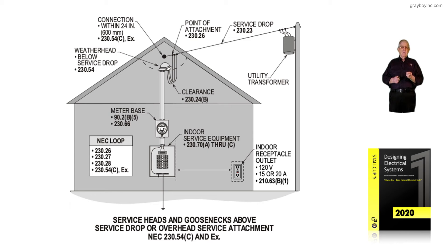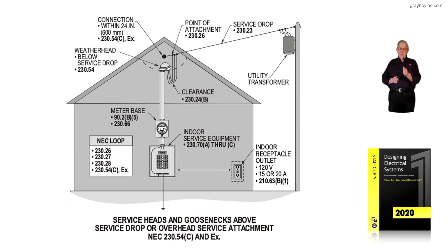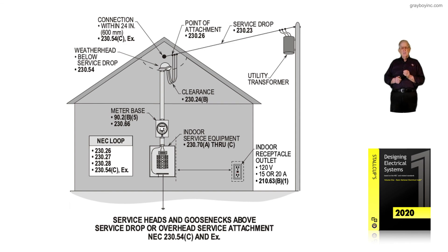The NEC loop recommends reviewing 230.26, 230.27, 230.28, and the exception to 230.54C, because due to the installation and construction of the building, you cannot place the drop 6 to 12 inches below the weatherhead and have the weatherhead above the point of attachment of the service drop. So figure 6-32b is illustrating the exception and the application of the exception to 230.54C.